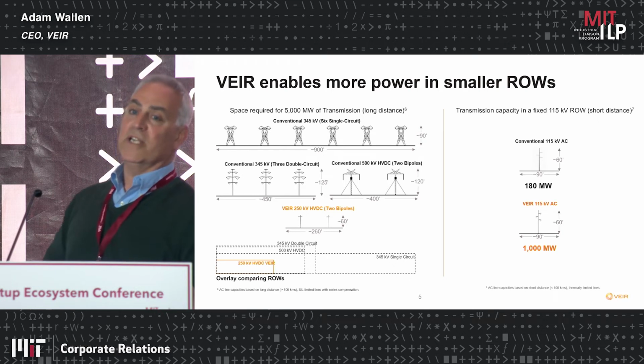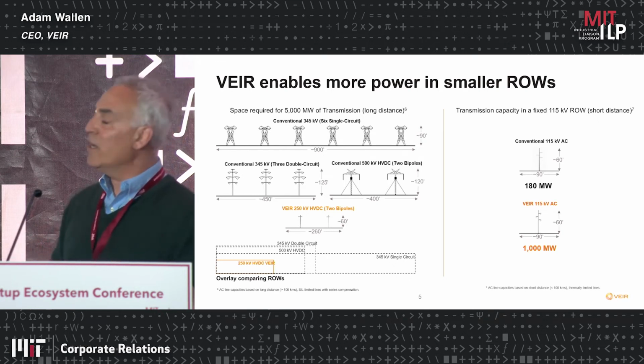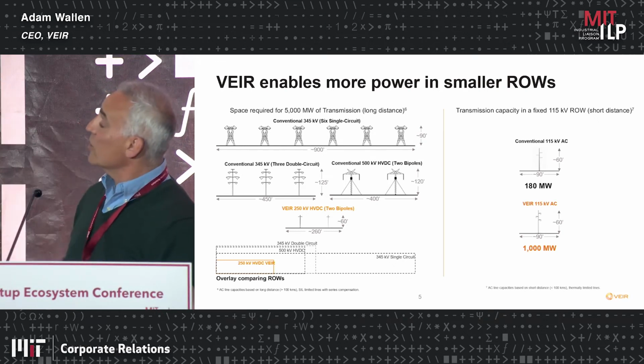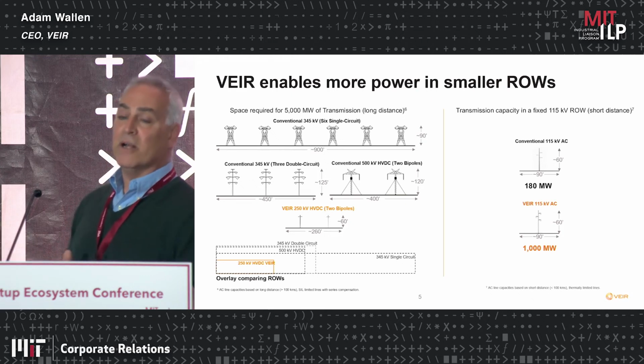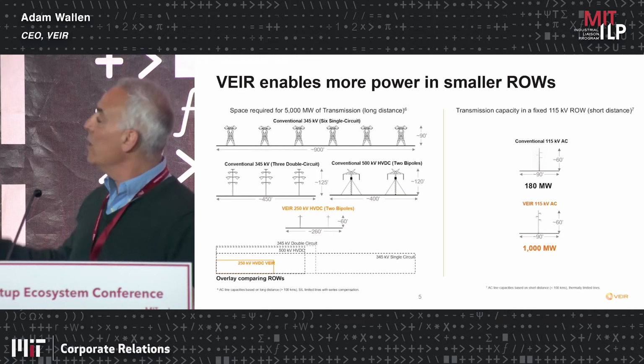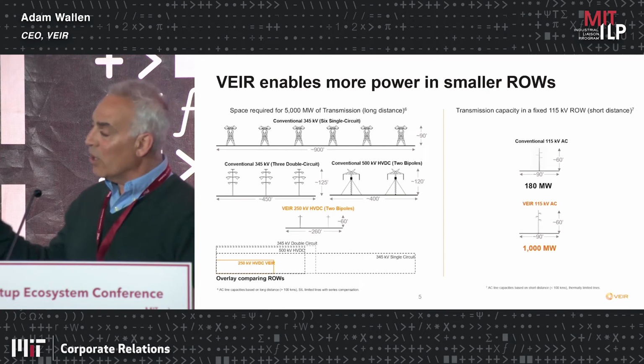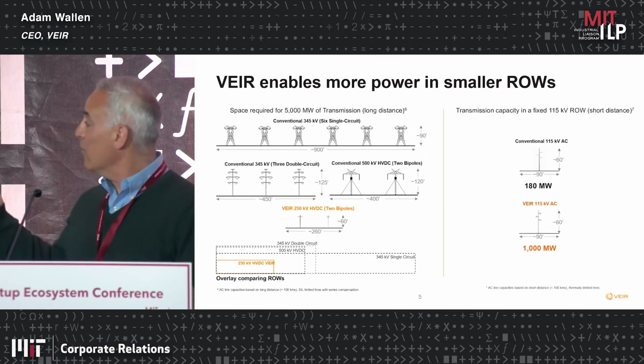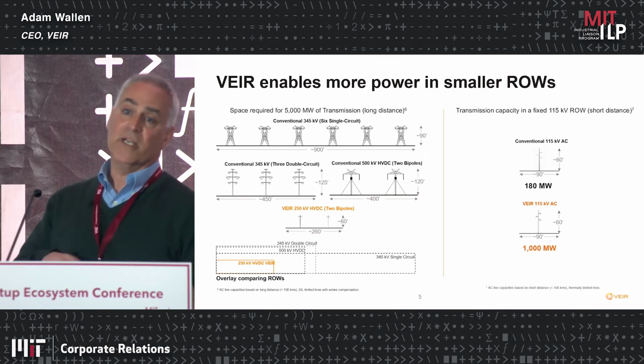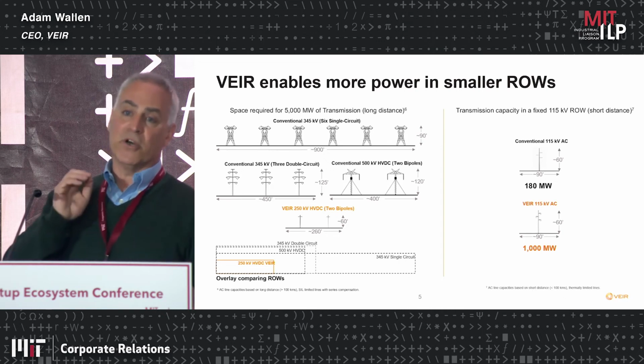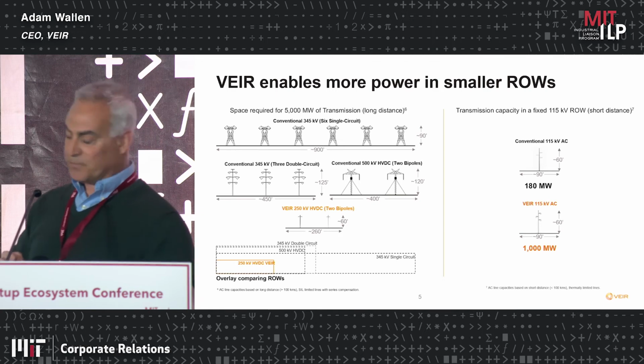A utility wants to increase the power they can get through that area. With a conventional conductor, they max out at about 180 megawatts. Reconductoring with our high voltage superconducting cables, you can get 1,000 megawatts—so simple numbers are 5x the power at the same voltage class.